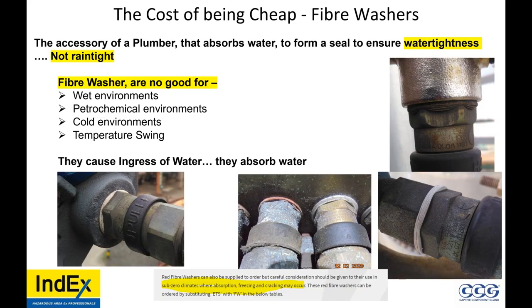Why do the manufacturers still sell fiber washers? Because some end users still unfortunately ask for it. If the manufacturer didn't provide the fiber washer, they then perhaps wouldn't get the job of selling their glands to that end user. Chicken and the egg. Does an IP66 device with an IP66 gland require an IP washer? Well, if you want anything greater than IP54, install the IP washer. If you don't have an IP washer, what is the point of buying a device that is IP66 and a gland that is IP66 if you're not going to maintain IP66?